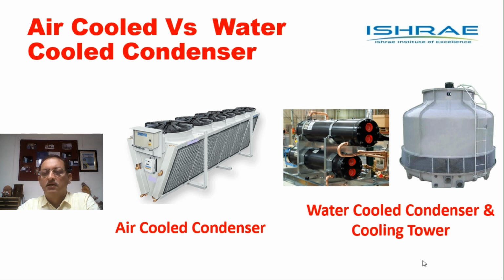On the other hand, right hand side, we can see the chiller plant, the condenser and evaporator, which has been kept on a single chassis, and along with the cooling tower which is required when we have a water cooled condenser. The cooling tower is required to be kept on rooftop, whereas the condenser is normally in this case kept in the machinery compartment along with the compressor and evaporator.